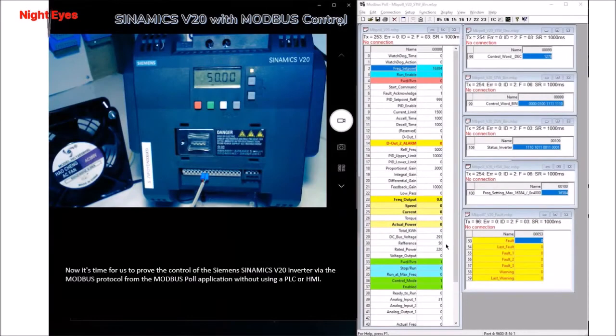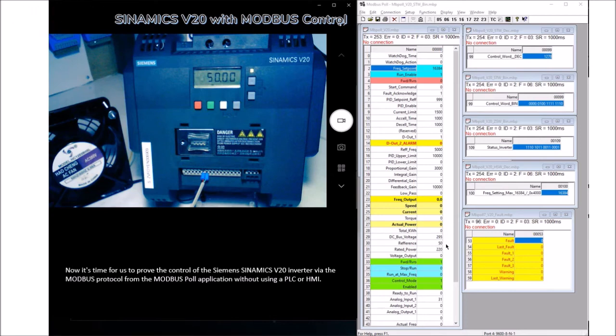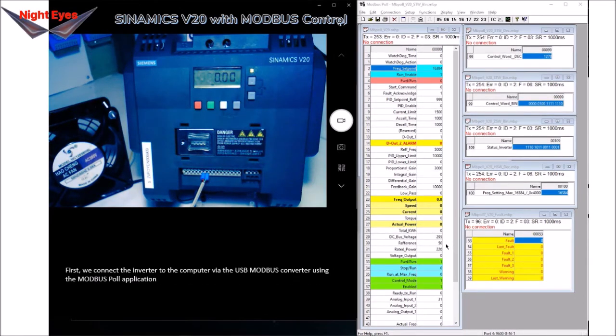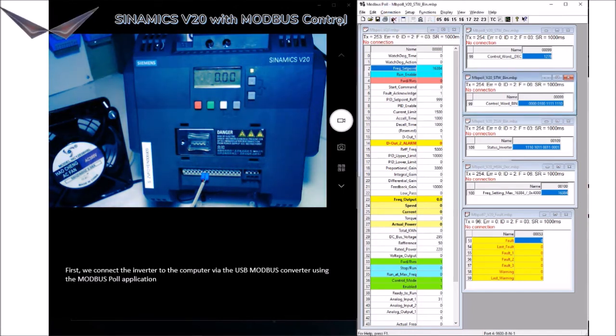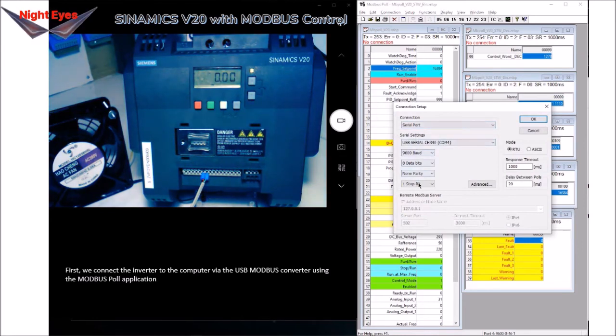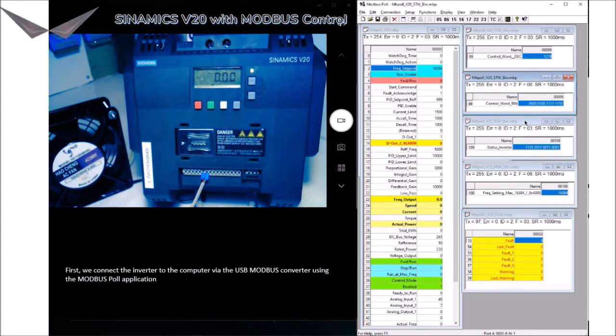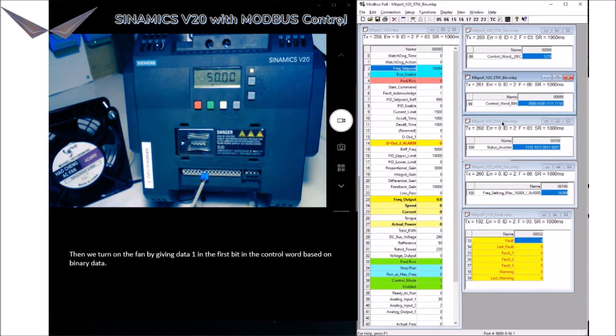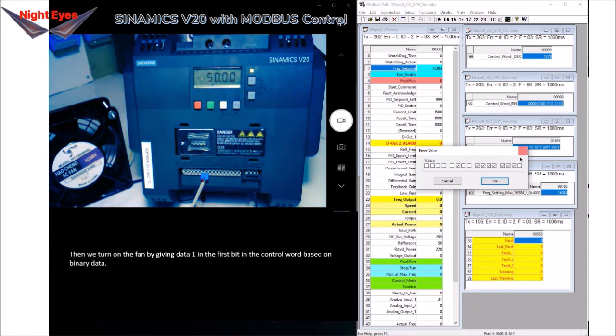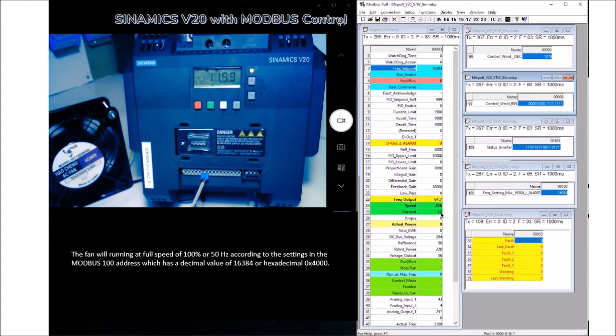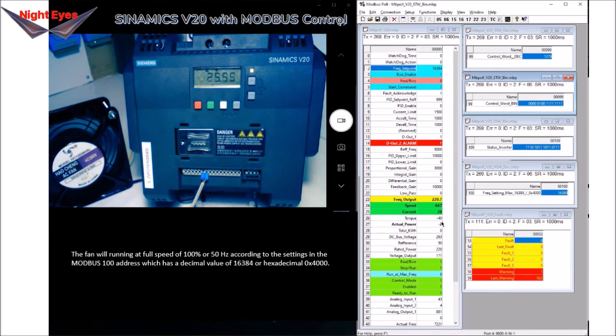Now it's time to prove control of the Siemens SINAMICS V20 inverter via the Modbus protocol from the Modbus Poll application without using a PLC or HMI. Connect the inverter to the computer via the USB Modbus converter using the Modbus Poll application. Turn on the fan by setting data 1 in the first bit of the control word in binary. The fan will run at full speed of 100% or 50Hz, according to the setting at Modbus address 100, which has a decimal value of 16384 or hexadecimal 0x4000.